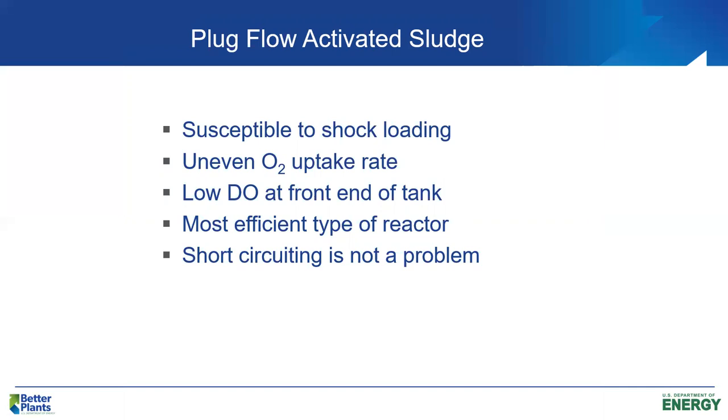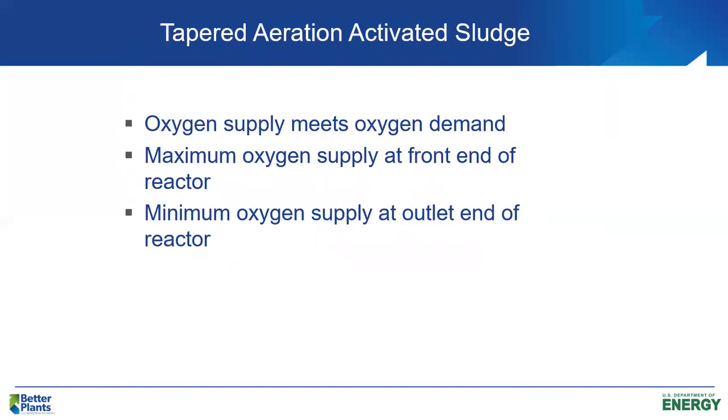So it has some drawbacks, but again, it's the most efficient type of reactor we have. And the main reason is that the wastewater does not short circuit the reactor. It stays in there pretty close to the hypothetical detention time.